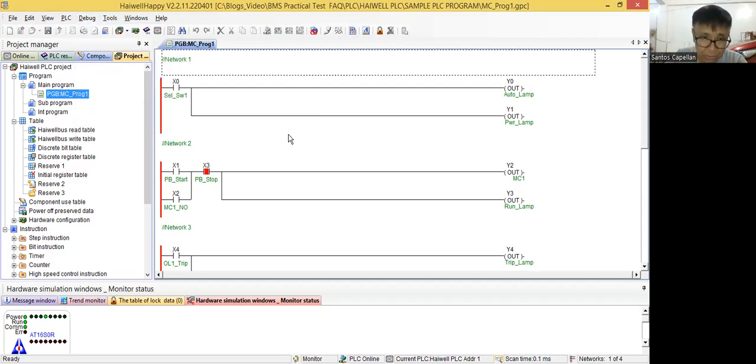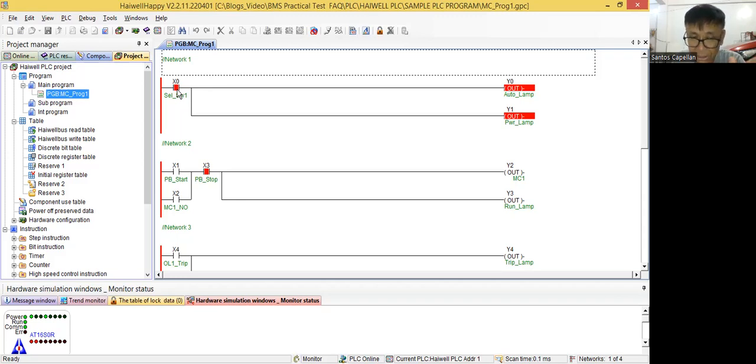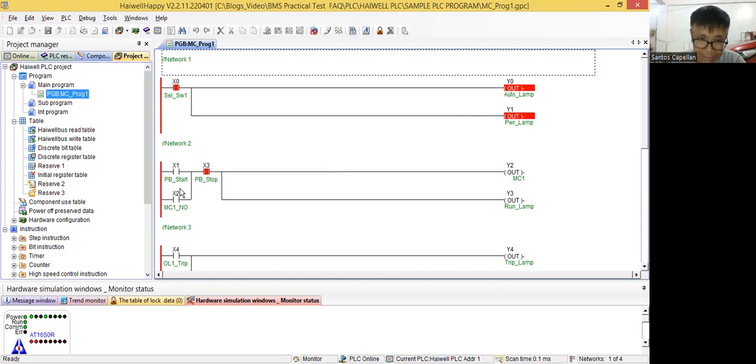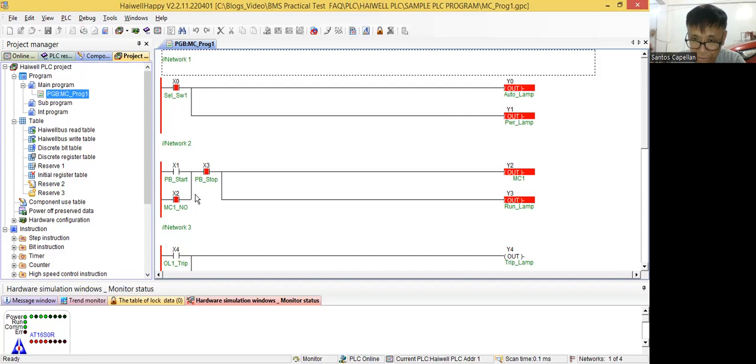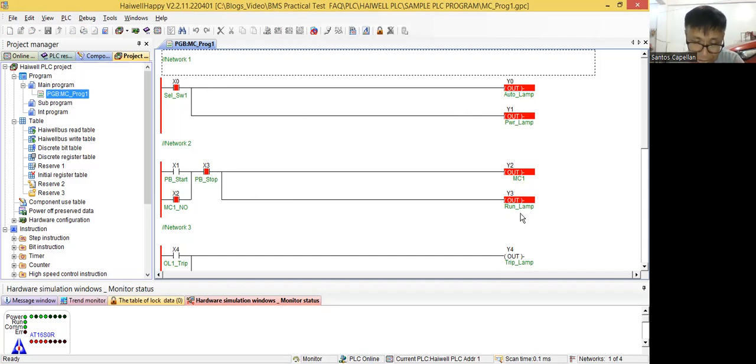Now let me show you again. So I will put in... As you can see the selector switch is in auto. Then this is being represented by the red color. Meaning this contact is closed. Then my output for auto lamp and power lamp is already lit. Then I can start the fan. Let me start it. So momentarily, this one closes, then the latch is working.